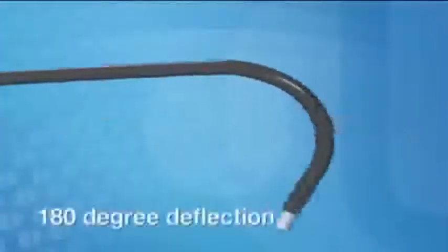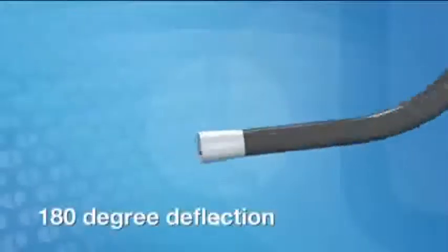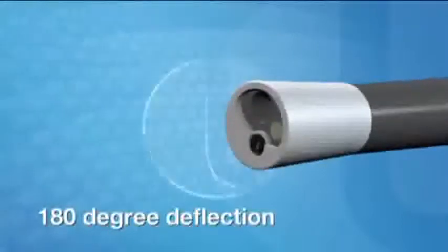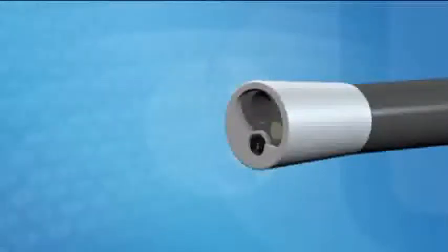The Polyscope offers a 180 degree deflection, allowing for optimal access and visualization in hard-to-reach anatomy where a flexible endoscope is necessary.